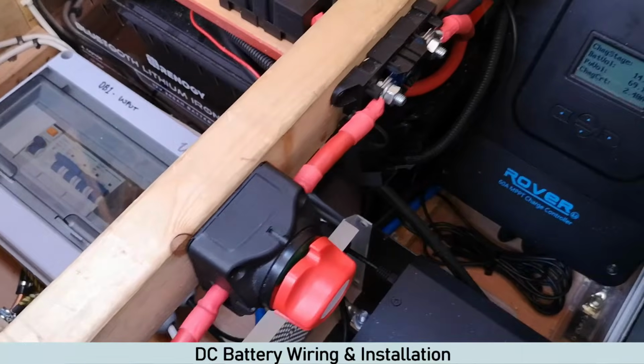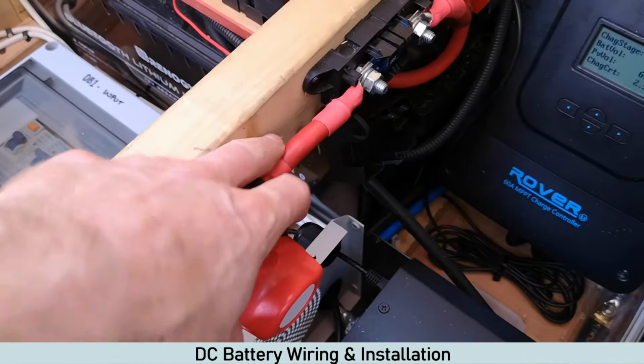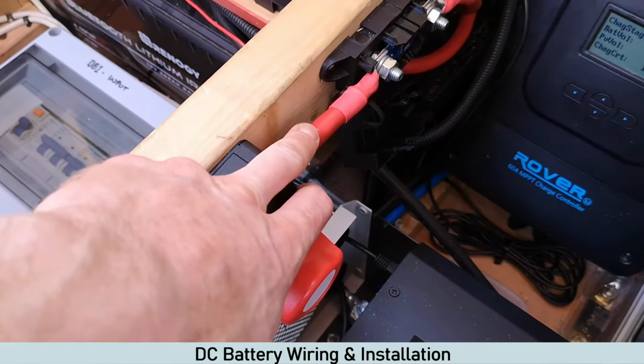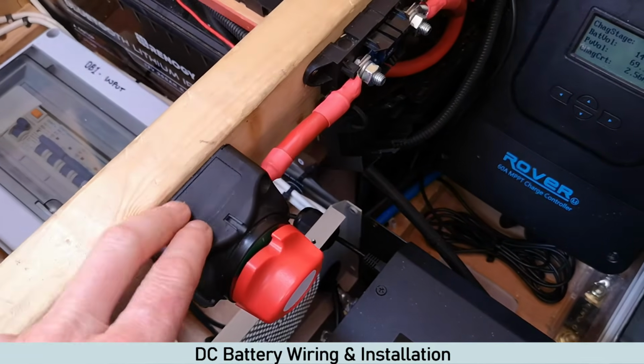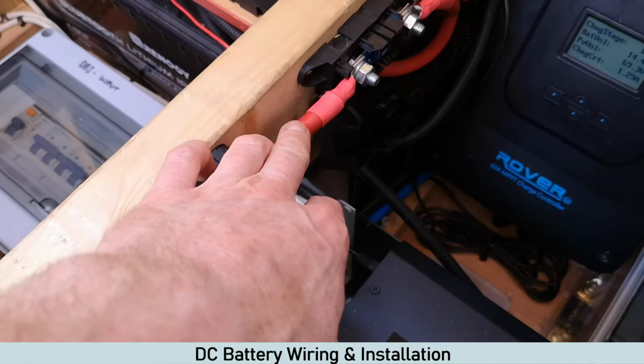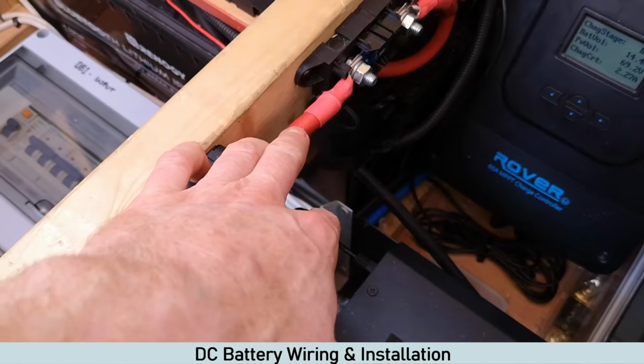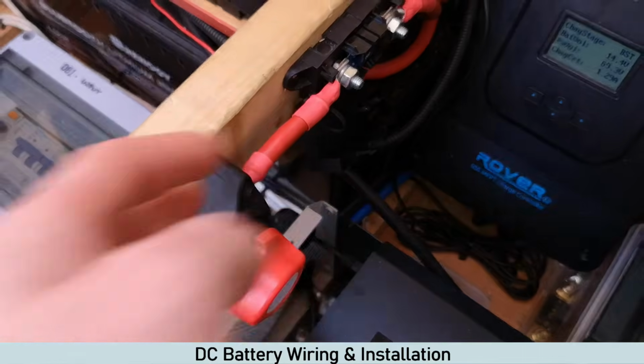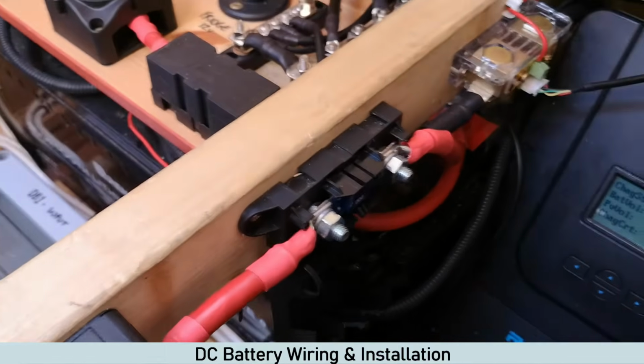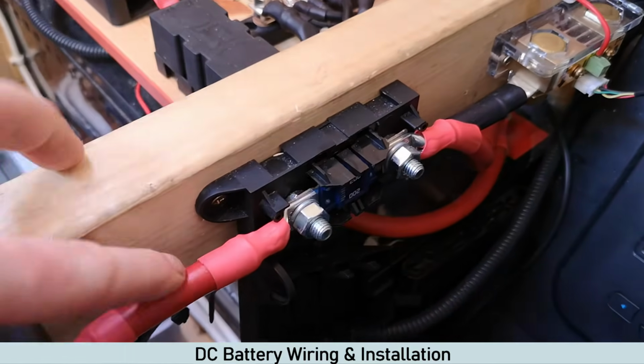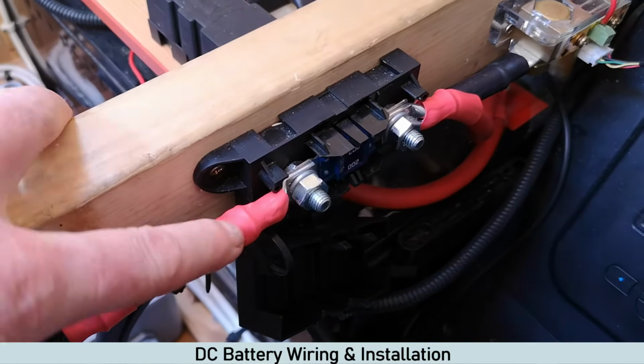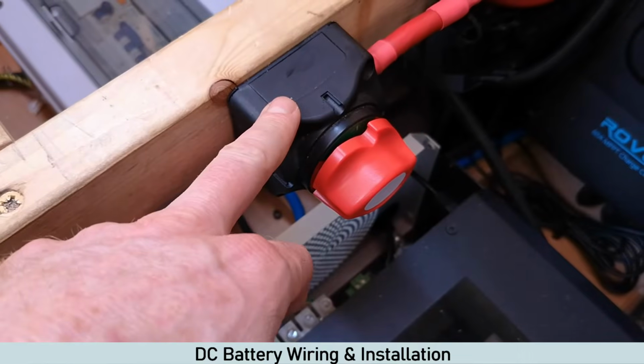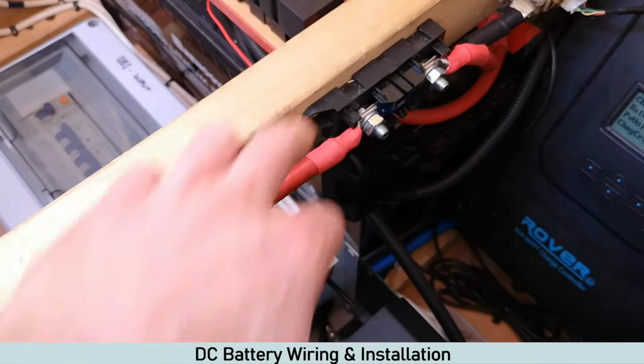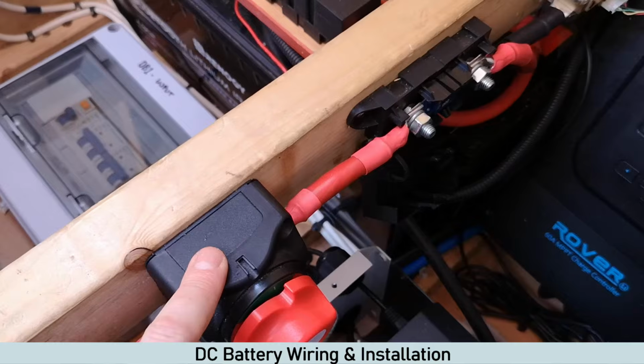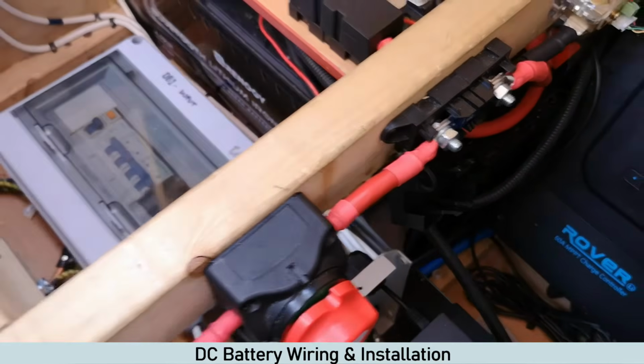Now obviously these figures are based on the cable we've used, which I'll put a link to in the description below so you can go and see that cable. But always go to the manufacturer instructions with cabling, because DC battery cables are slightly different in the amount of amperage they can pull. Now obviously your fuse needs to be less than the max rating of your cables to ensure that the fuse blows before the cable burns out. And then your isolator needs to be rated higher than your fuse to ensure obviously that this can withstand the power before the fuse blows.